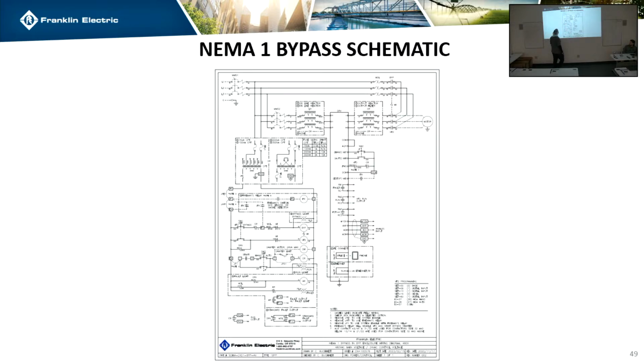So most of the time, you're going to see it has a line reactor. You're going to see one of the transformers checked off. We do have a Fireman's relay option. I think it's kind of rare though. People don't order that much. Most of the Fireman's override stuff you can do in the programming. So this is if you're adding physical Fireman relay components. Yeah, sometimes we do that. I just had a thing they needed that. So it's available. It's just not super common. And then almost all of our bypass panels are going to come with run pilot lights, fault pilot lights, and bypass lights. And then the Bluetooth is right here.